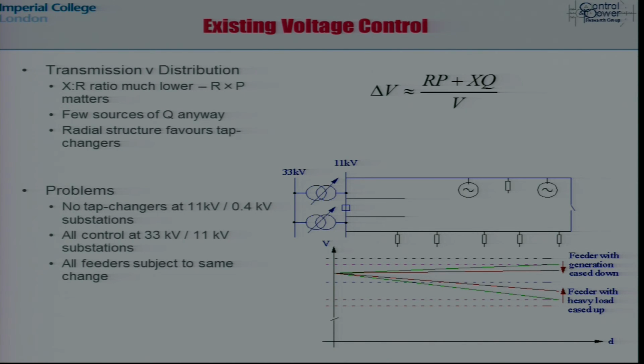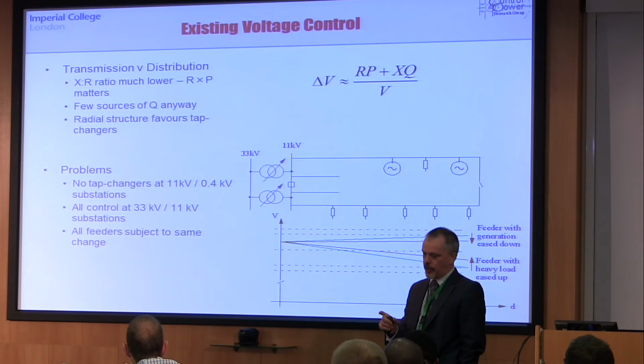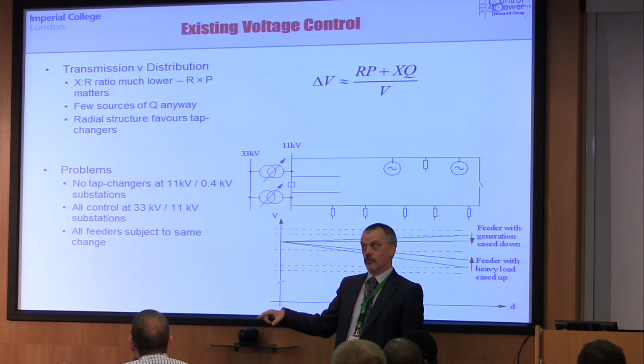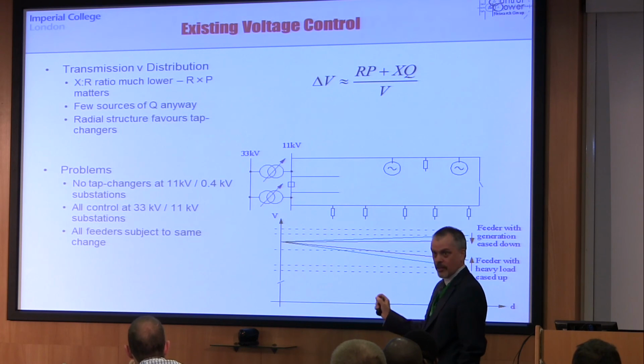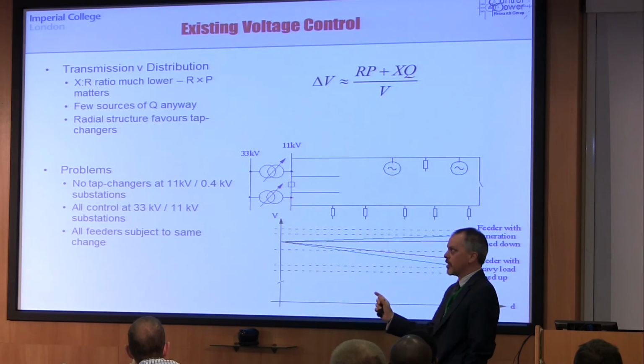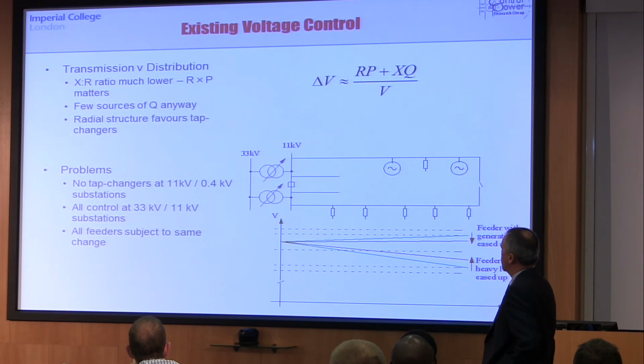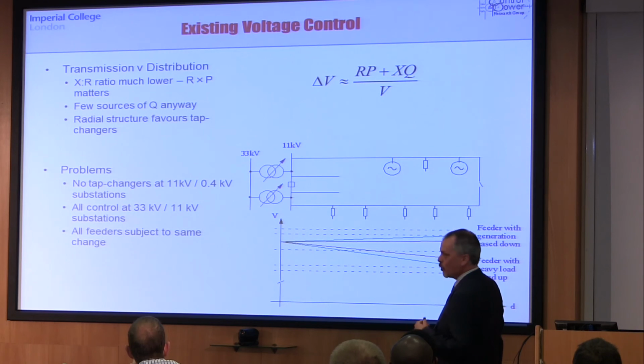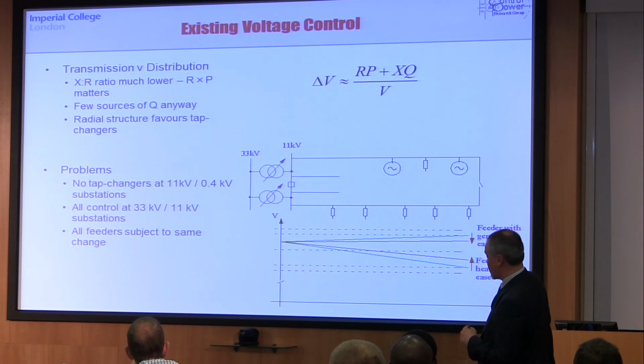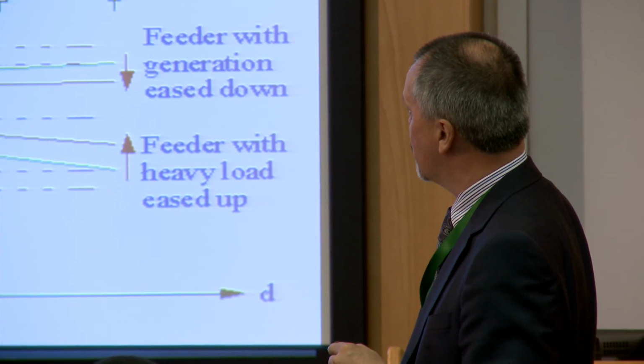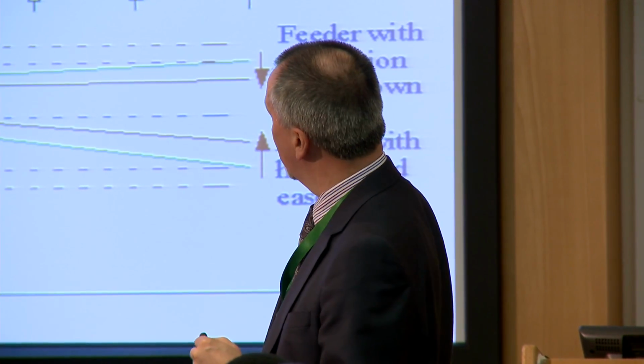Looking at what the opportunities are, we'll start by just pointing out some differences between transmission networks and distribution networks. First of all, the X to R ratio is much lower. So that's the ratio of the inductive reactance of the cables to the resistance. We've brought the conductors closer together as the voltages have got lower, because the insulation requirement is down, and that means the inductive reactance is down. And that changes our view of that equation, the equation for a voltage drop along the line. Our colleagues in transmission networks just concentrate on the reactive power term because the reactance is big and the resistance is small. But as we go down in voltage levels, these two become either comparable or dominated by the resistive term. And that changes the way we do things.